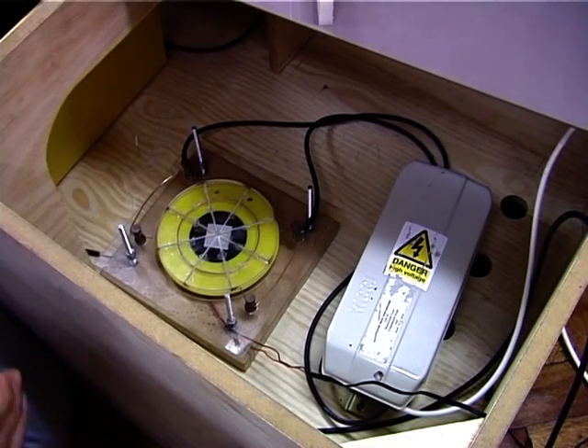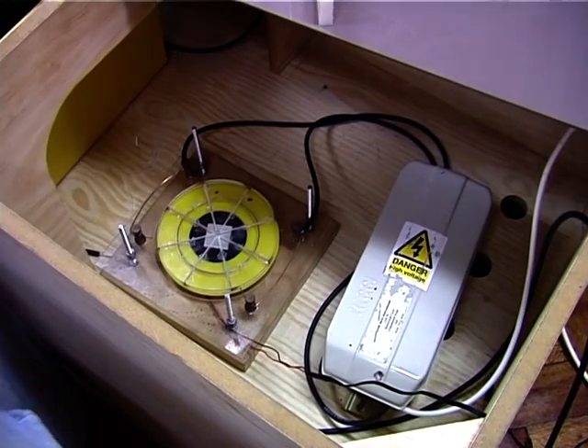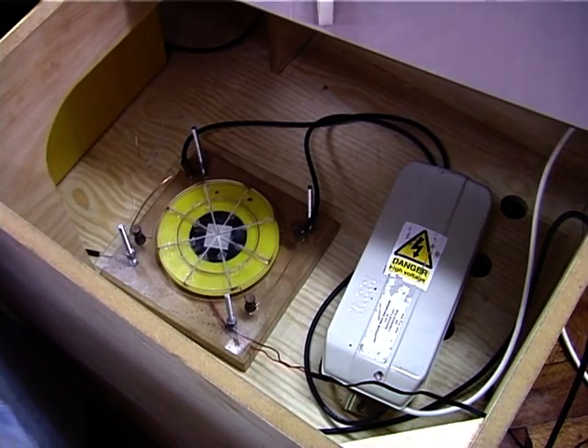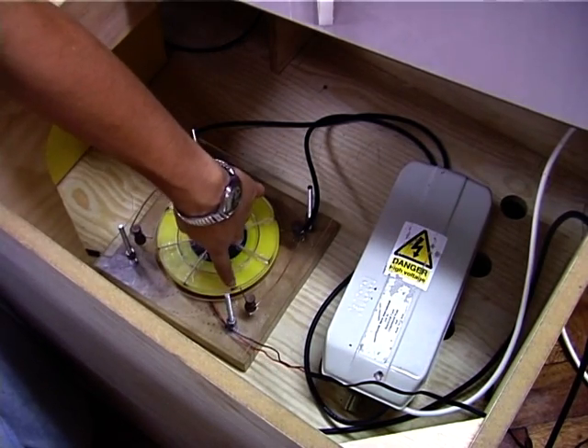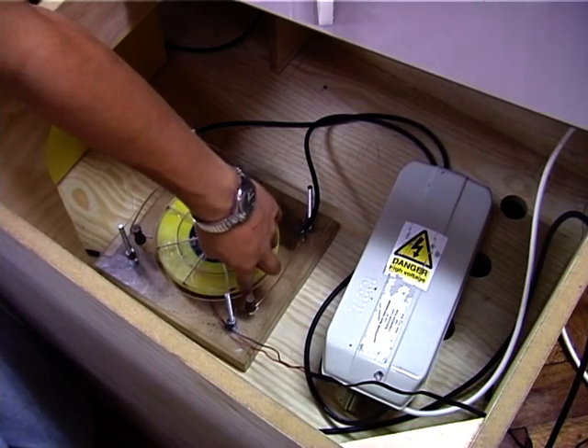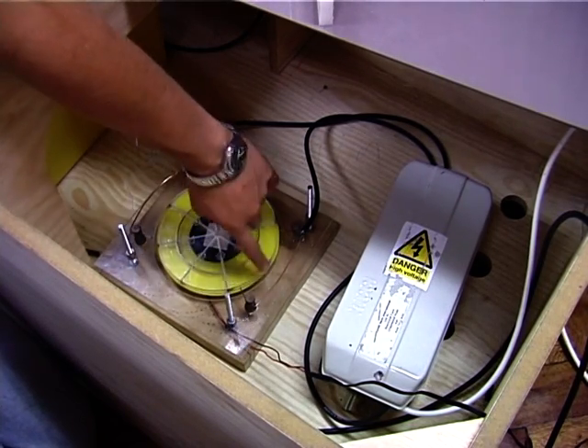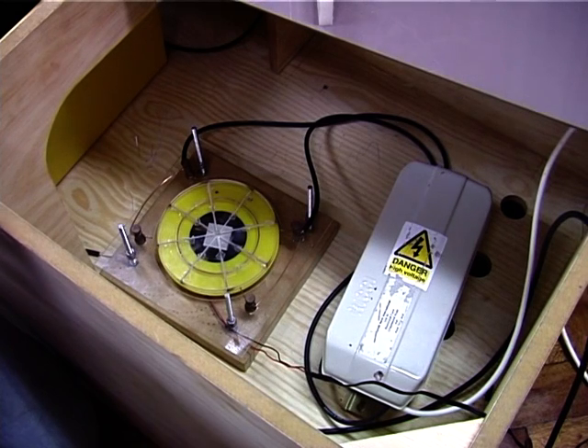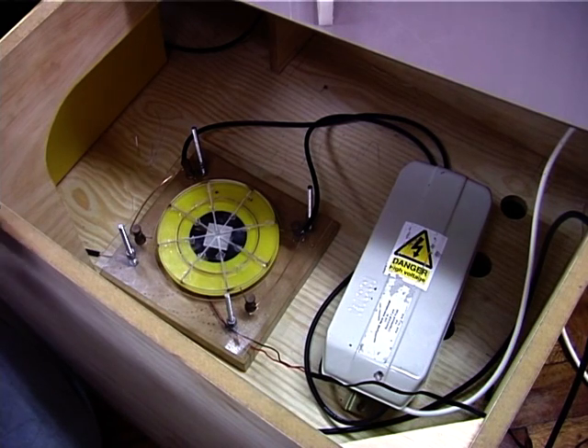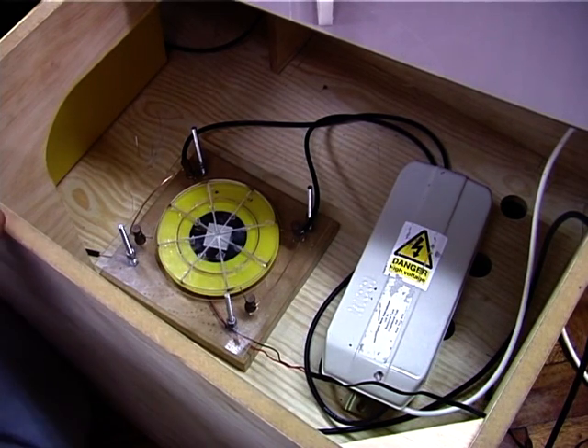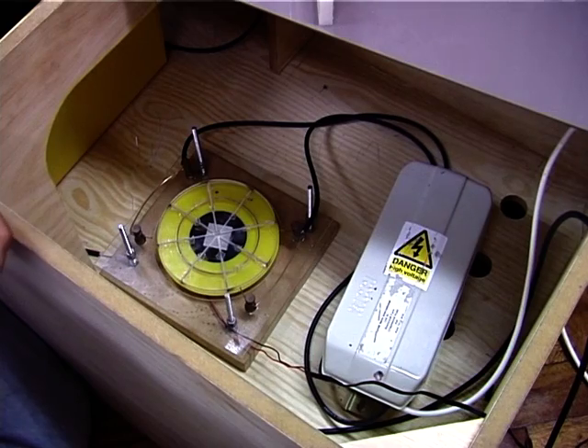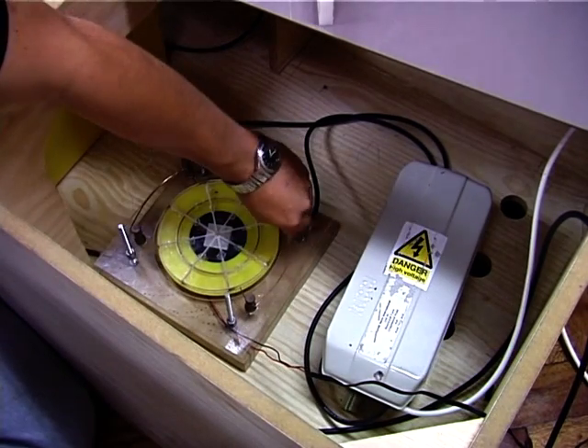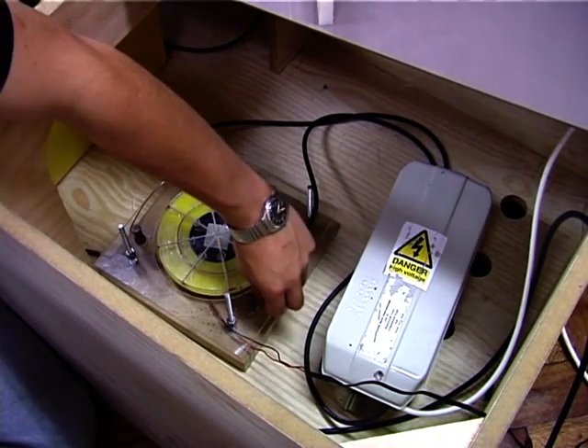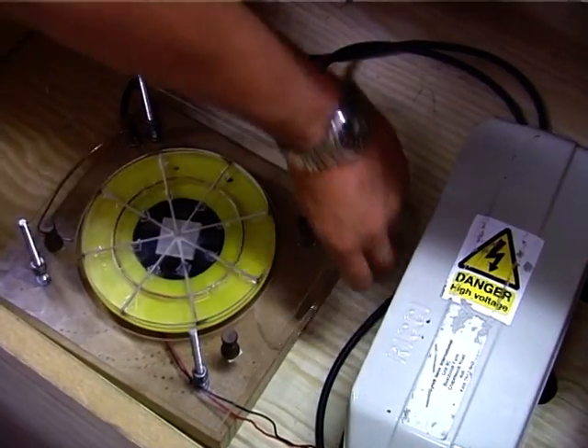Okay, I'm just about to actually change the electrodes on the spark gap. You can see here the blackened marks on the tips there and around the perspex disc. This is just a build-up of copper oxide. The simplest way to do it, since it's designed to be cleaned up easily, is actually just to replace the copper in there. So just unscrew these, pull that out.